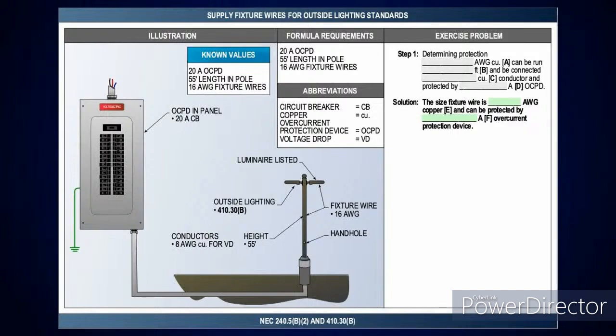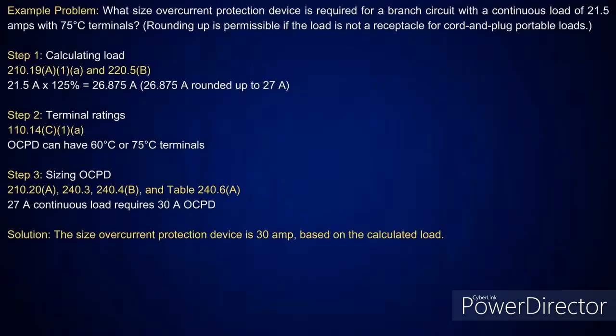And then here's one here. You got number 16 fixture wires with a 55 foot length pole with 20 amp overcurrent devices. What size conductors are going over there? Well, looky here. We're making you think here, because I'm going all the way over here and I had to upsize those conductors due to voltage drop, and I've got a number 8 conductor. Can I do this? You see what I'm saying? You got to go look at 240.5(B)(2) to make that determination. And you'd have to bond with the number 8 minimum conductor too. We're almost done with this thing, believe it or not.